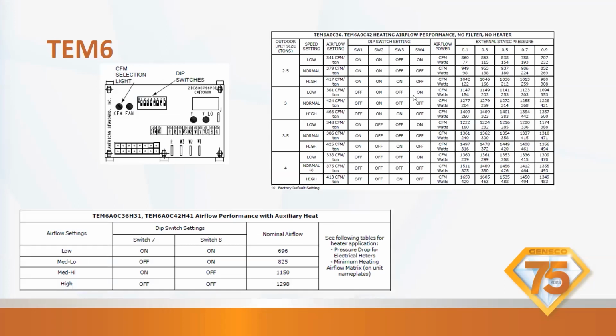This one is for a TEM6, which is a variable speed unit. Again, static pressure on the right. We're going to have our dip switch settings. We're going to have our tonnage, and we are going to set it according to our static pressure. We're also going to look at our airflow matrix on the nameplate of the electric heat, and it's also going to give us a static pressure differential.